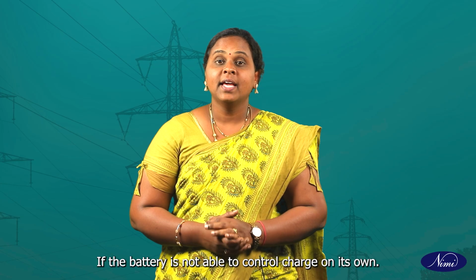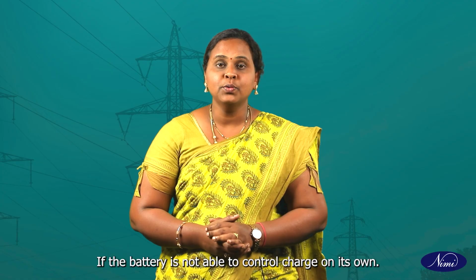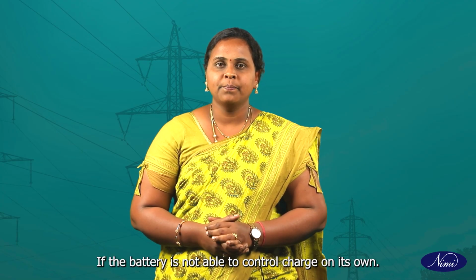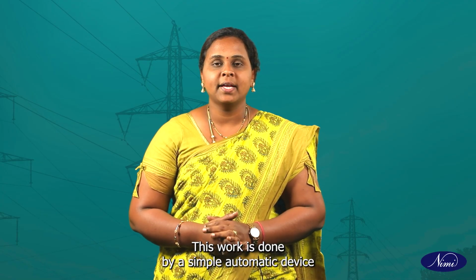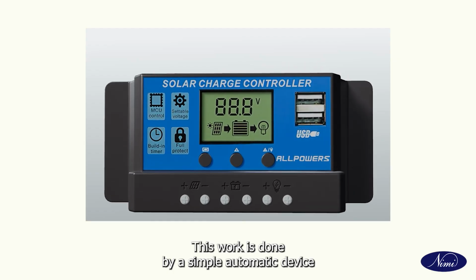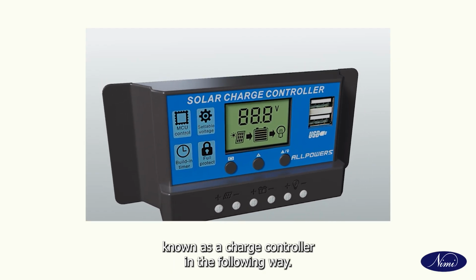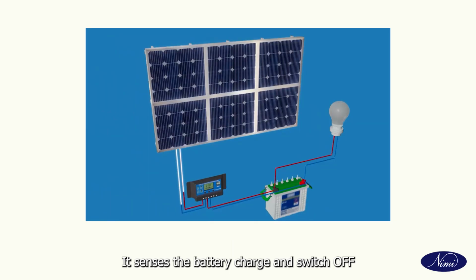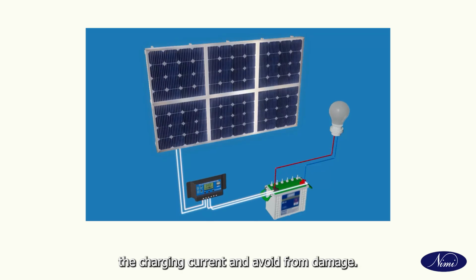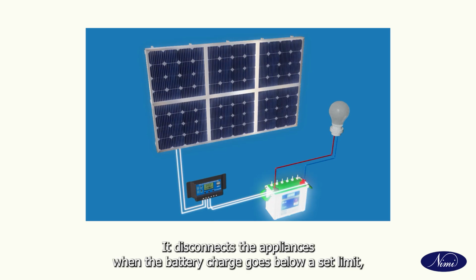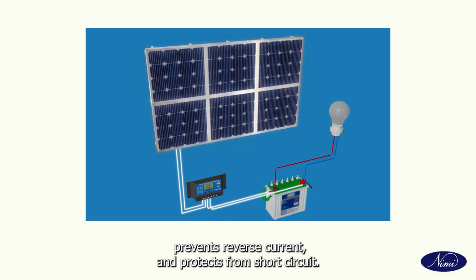Charge controller. If the battery is not able to control charge on its own, this work is done by a simple automatic device known as a charge controller in the following way. It senses the battery charge and switches off the charging current to avoid damage. It disconnects the appliances when the battery charge goes below a set limit, prevents reverse current and protects from short circuit.